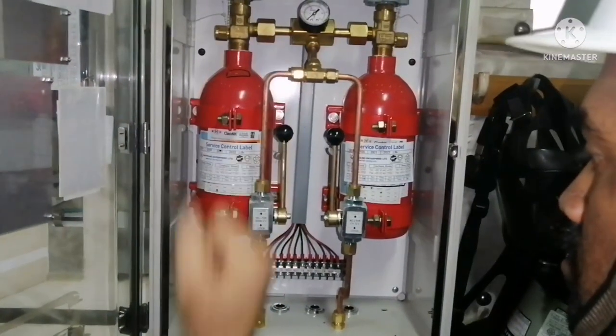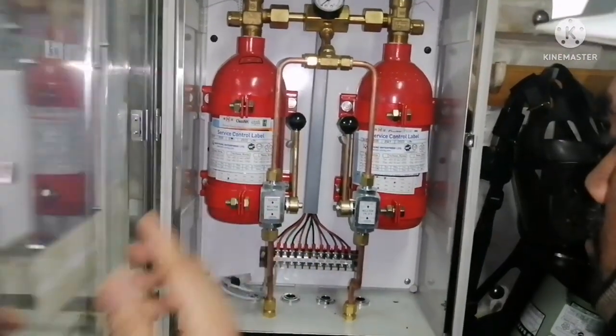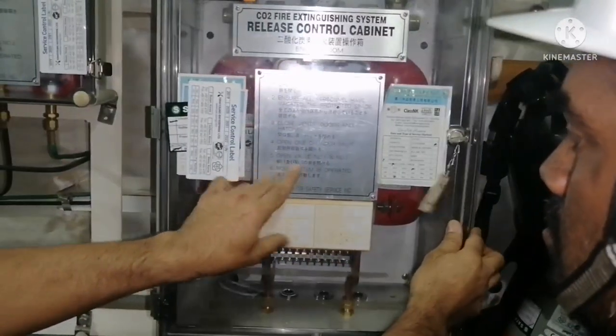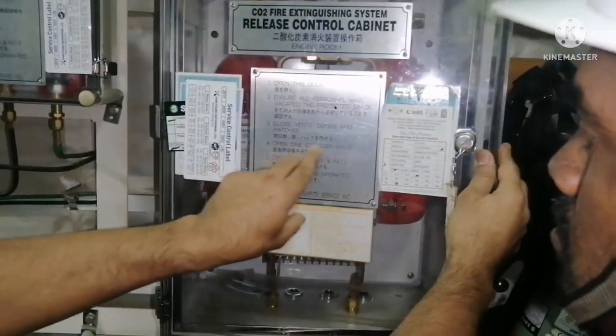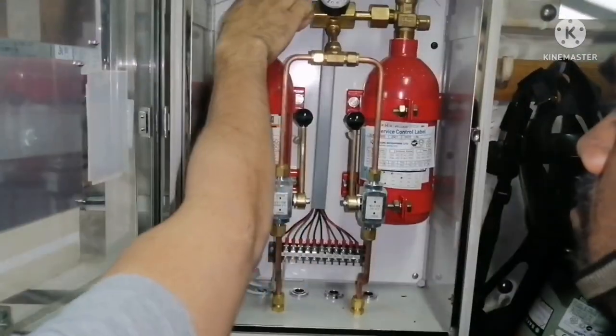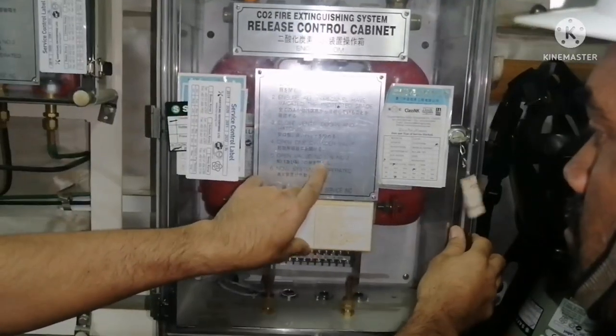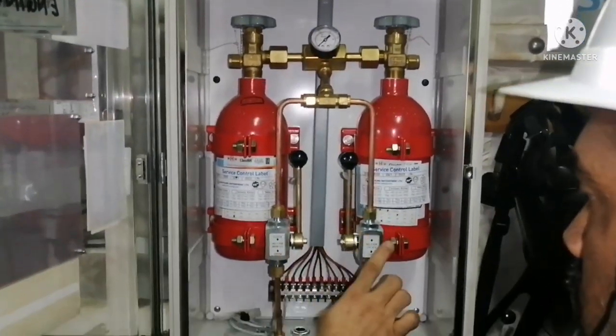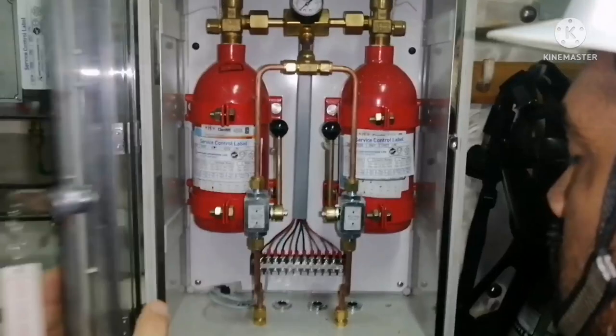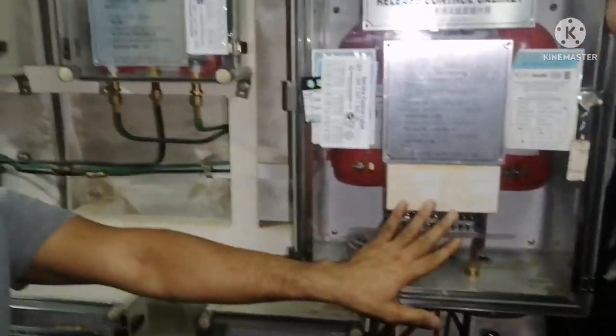Cut it. When you pull, it will cut by itself — it is not very strong. Once this is opened, you can see open number one and number two valve. This open one cylinder valve is this valve here — this is the first valve. Open this, then open number one and number two cylinder valve. This valve will activate the CO2 firefighting system for the engine room.